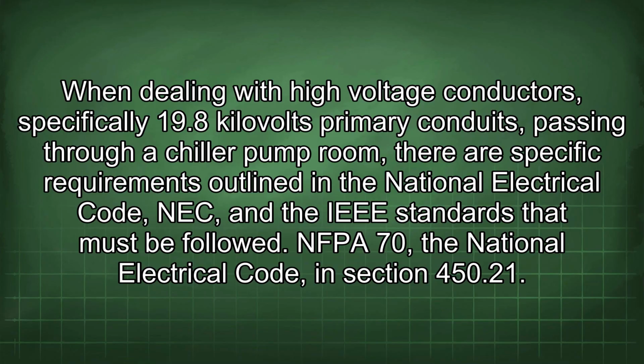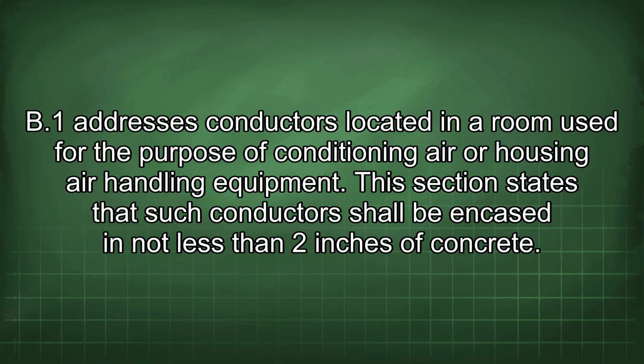When dealing with high voltage conductors, specifically 19.8 kV primary conduits, passing through a chiller pump room, there are specific requirements outlined in the National Electrical Code, NEC, and the IEEE standards that must be followed. NFPA 70, the National Electrical Code, in section 450.21.B1 addresses conductors located in a room used for the purpose of conditioning air or housing air handling equipment. This section states that such conductors shall be encased in not less than 2 inches of concrete.